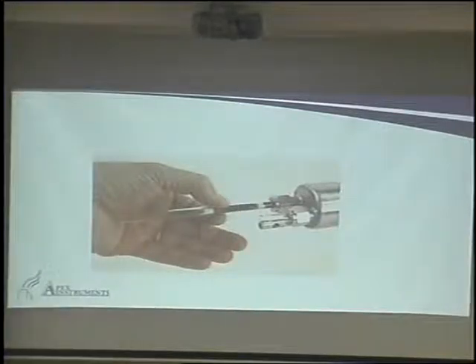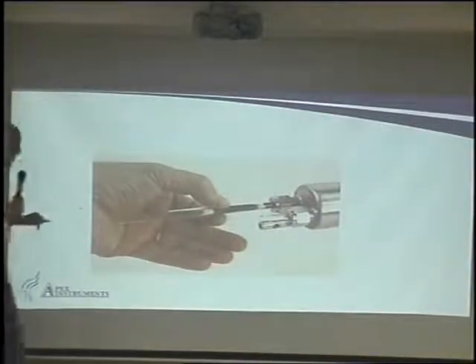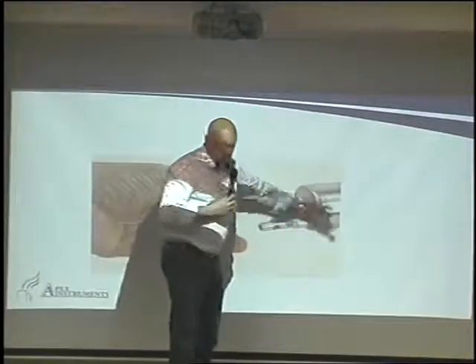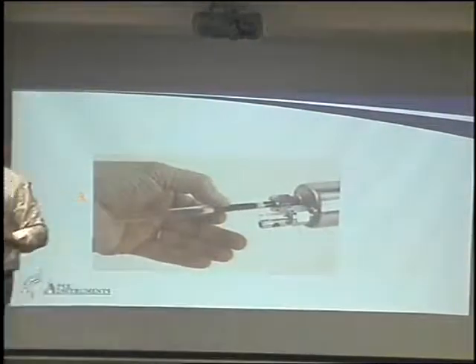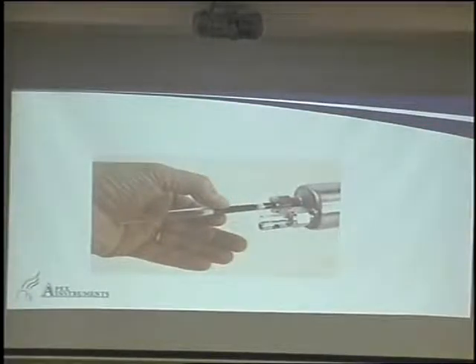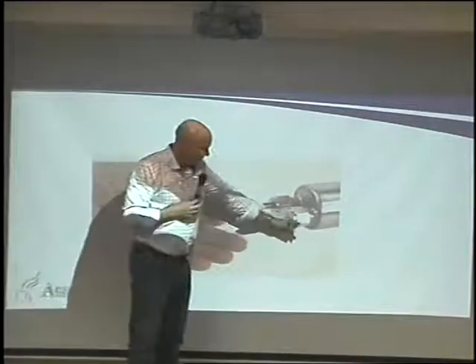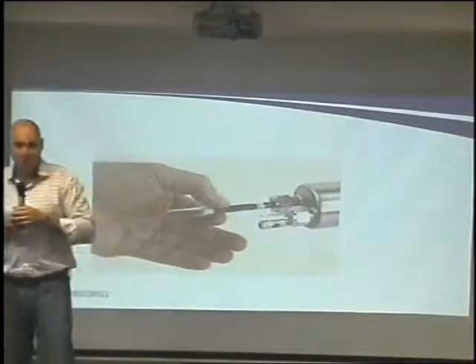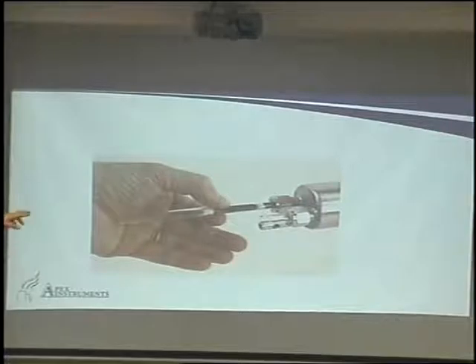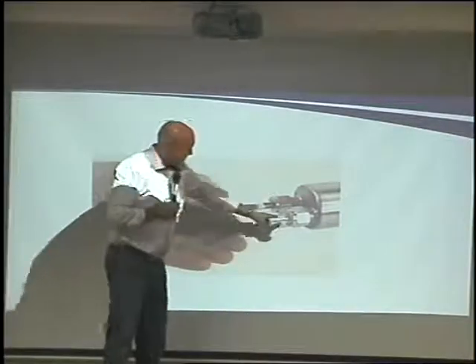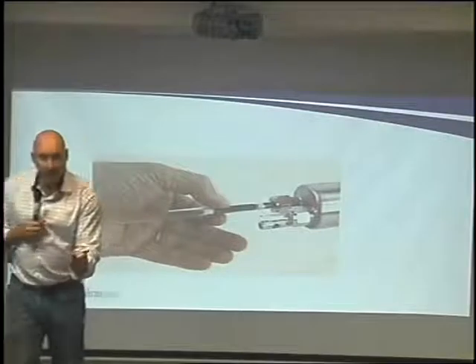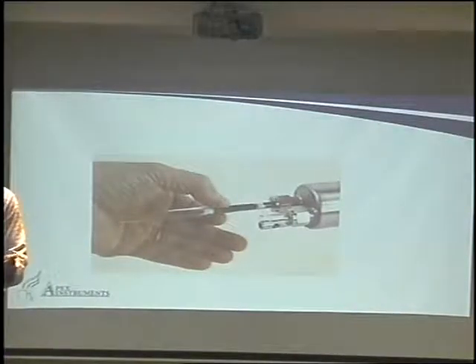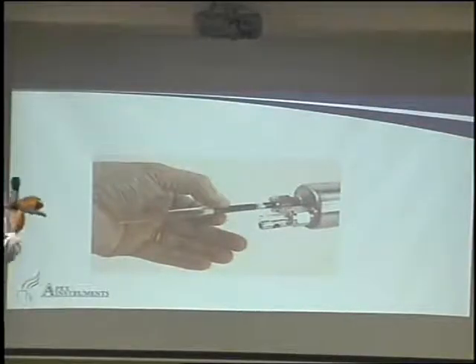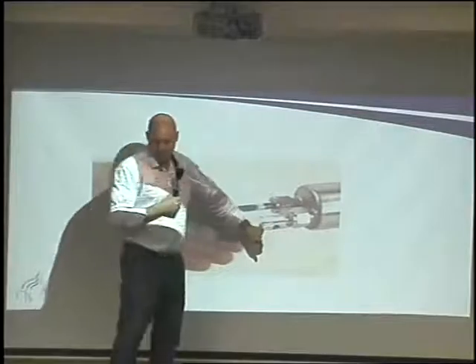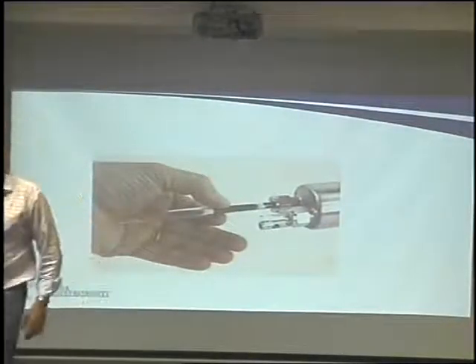So this is a picture at the beginning at the front of the probe. So you're going to install your traps that'll sit down inside the probe on A side and B side. And you connect them here with just a nut and a ferrule to keep them nice and tight, okay? They're going to stick out maybe about this much in the front, so the tube is in the flow of the gas itself, okay? And then this guy here, this is just your temperature, your thermocouple reading for that probe, okay?